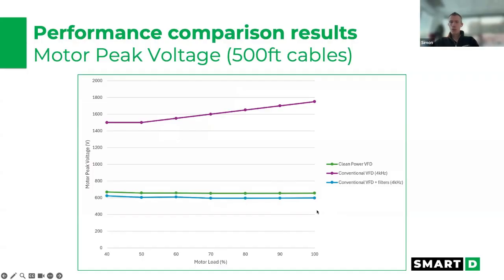And someone could point out that, well, Simon, the clean power VFD is a little bit higher than your sine wave filter equivalent. And that's true, actually, because your sine wave filter is a big chunk of metal you're putting outside, you're inducing a bigger voltage drop. And certainly in the context of long cables, voltage drop is something you try to fight here. So this is with 500 feet of cable.